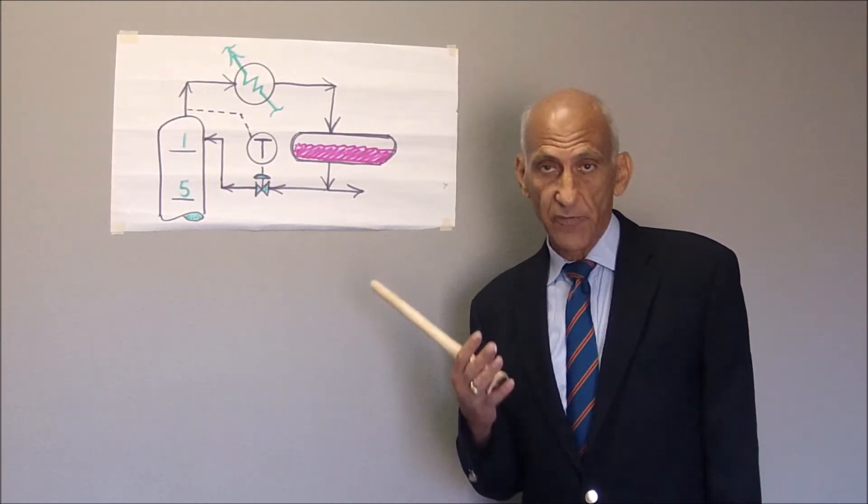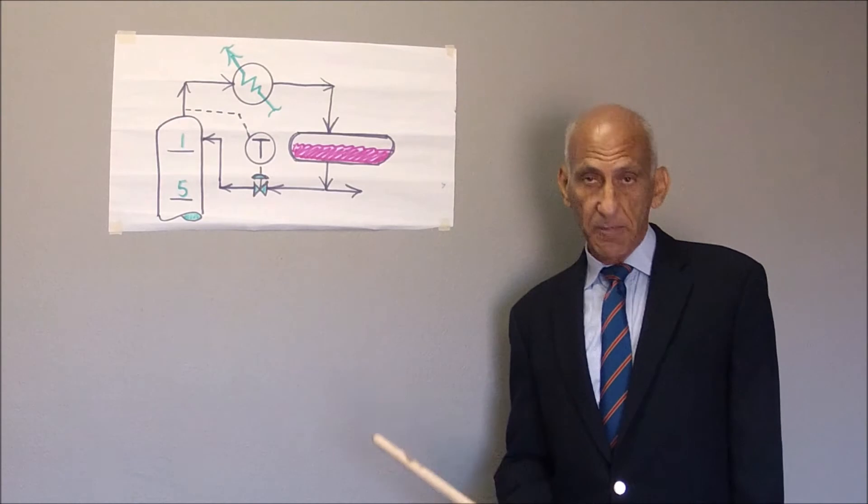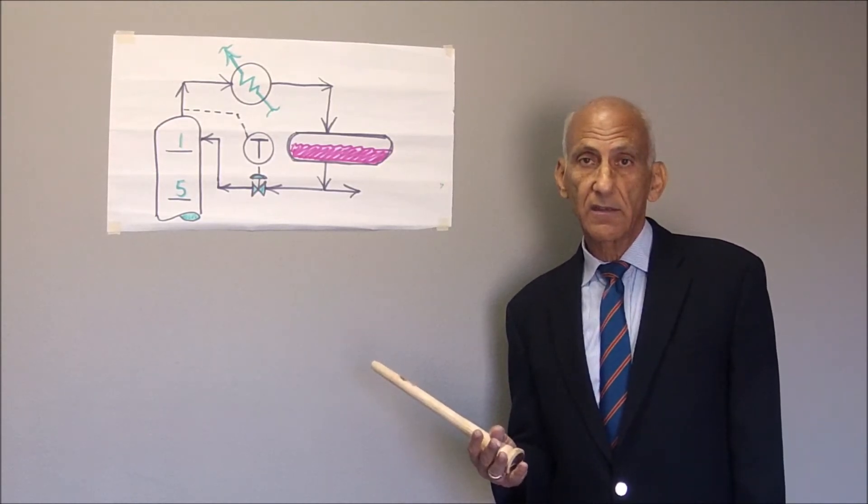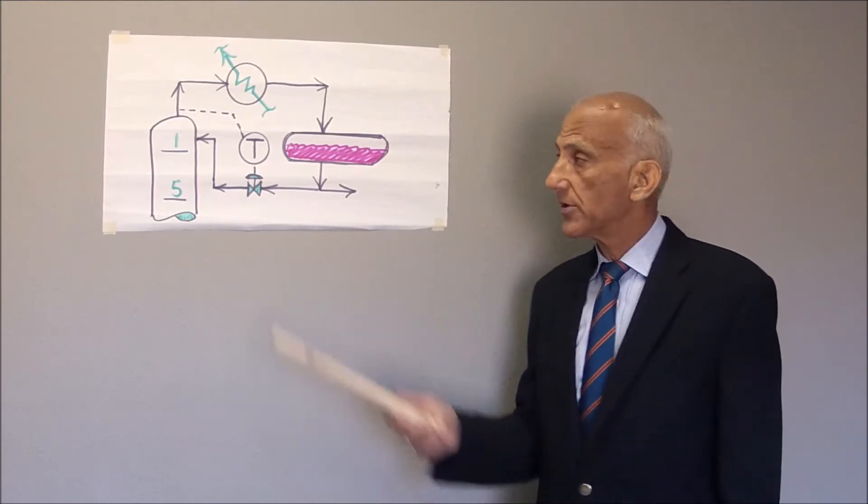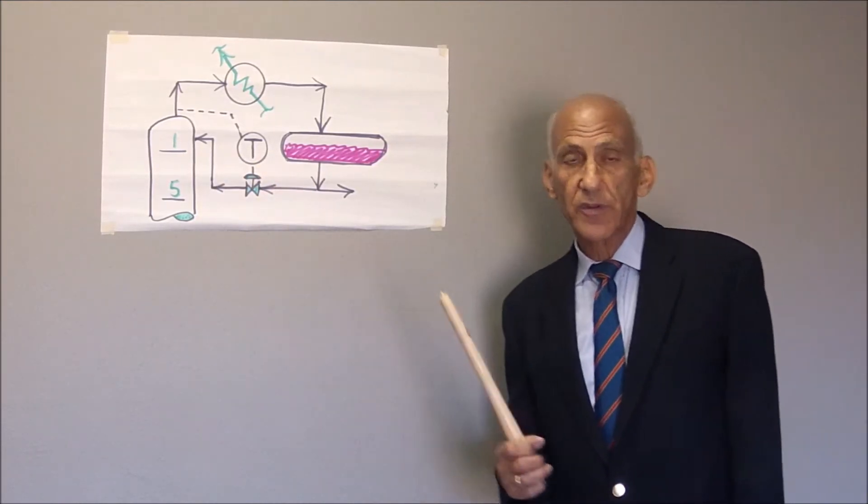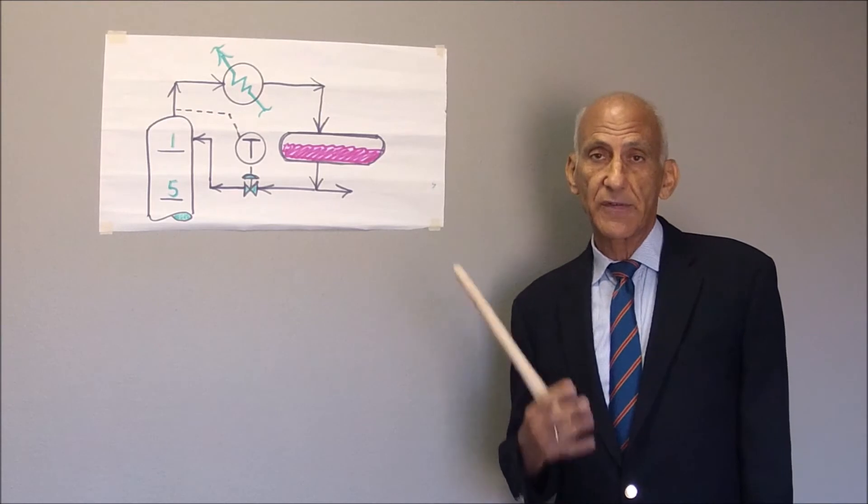This then increases the vapor flow through the tray, which increases the vapor pressure drop flowing through the top tray, which will then promote higher levels of entrainment.